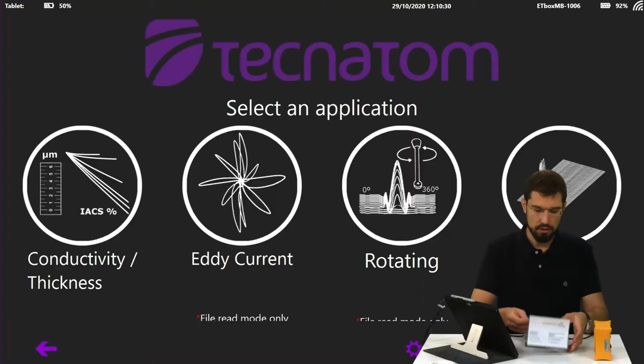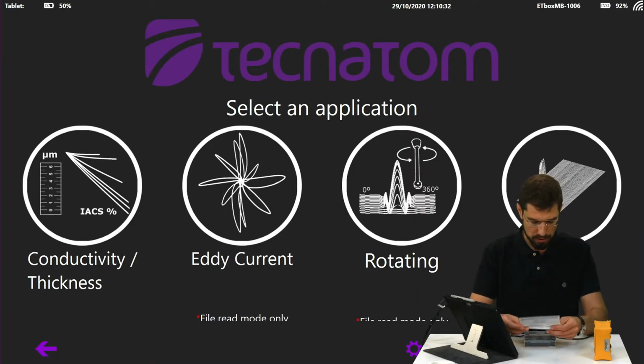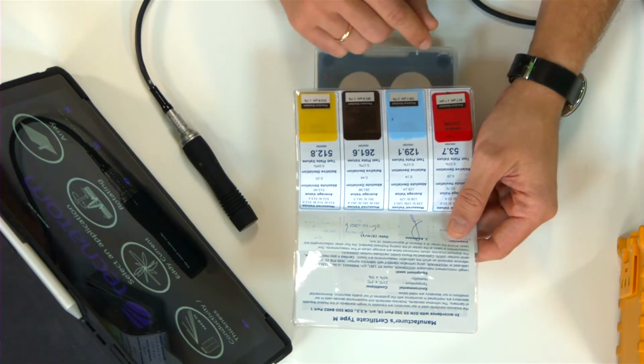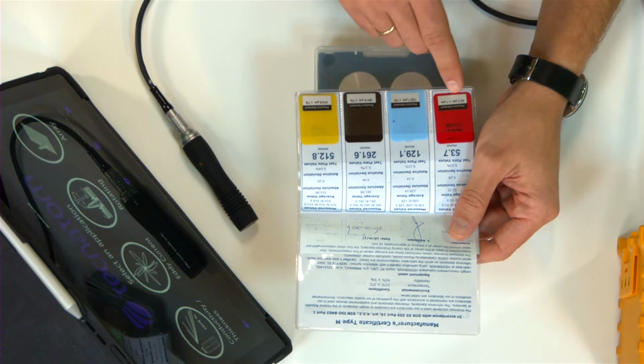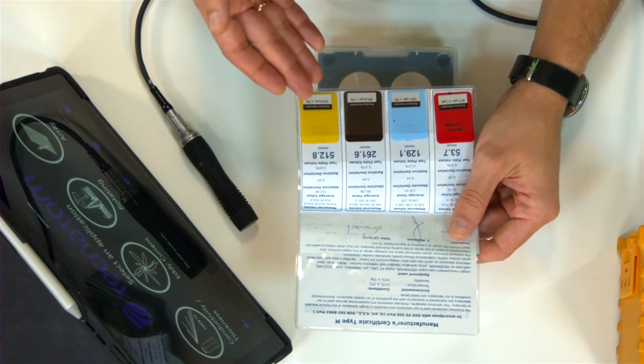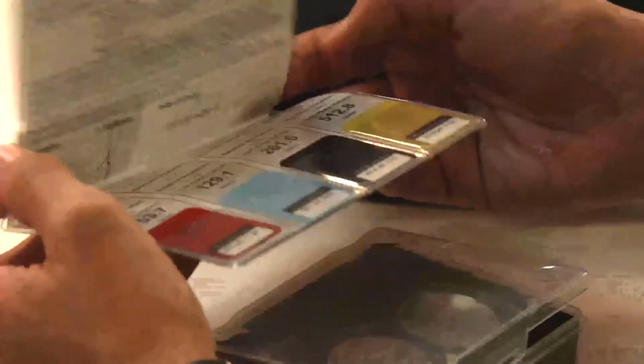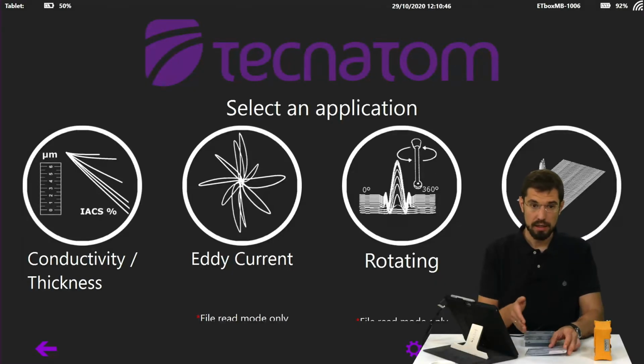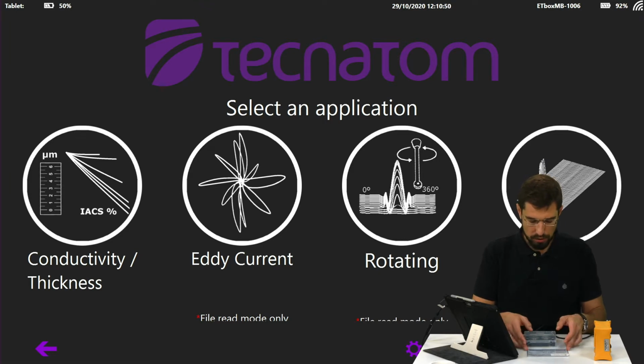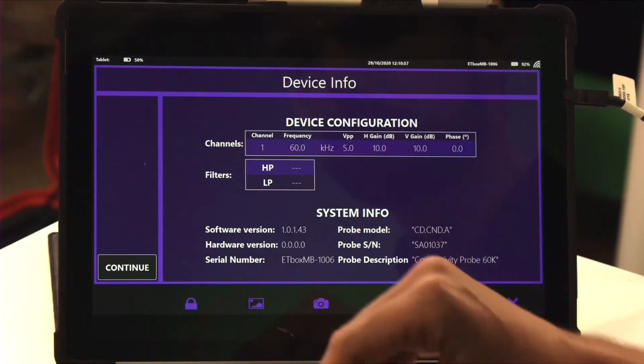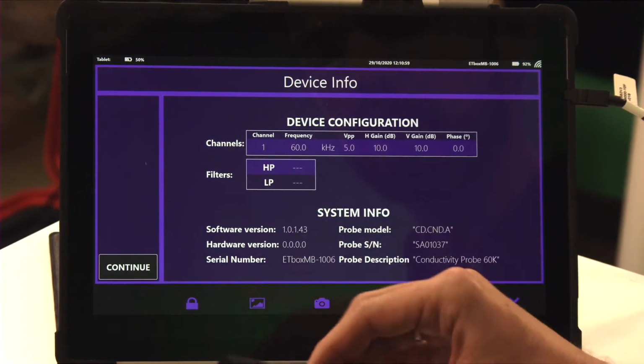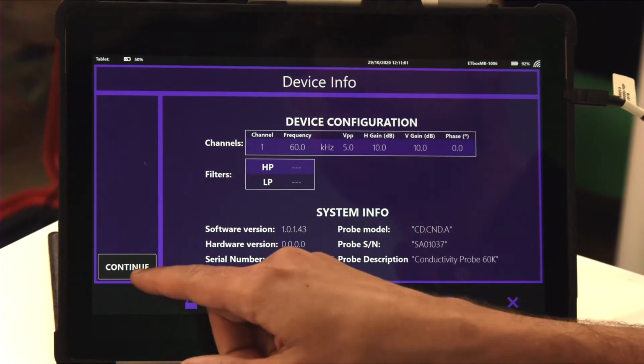On the other hand, for the thickness test, we have several certified patterns with different thicknesses. In this case, we've got gauges that go from 53.7 to 512.8 microns, depending on the range we want to work with, as we will need different gauges to work with different thicknesses. Moving on, let's start our conductivity thickness application. It has identified directly the probe we have connected.